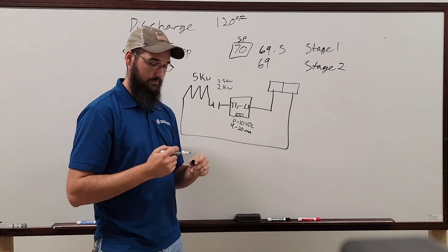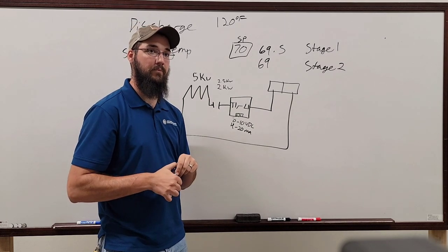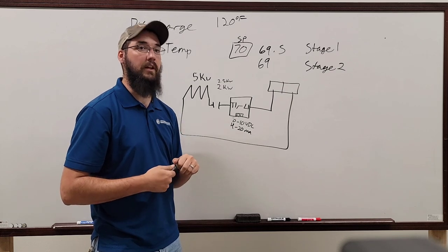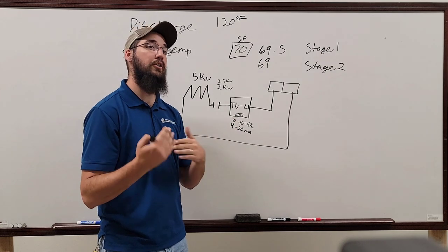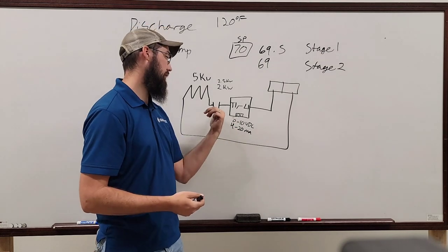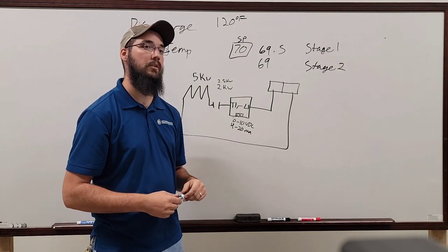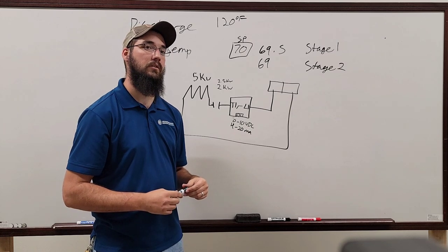So as soon as you get a call for heat, the contactor is going to slam, but your SCR is still going to regulate. Yes. And that's one way to know if you have a heat call: if all your heat safeties are closed, this contactor will close. If not, you have a control voltage issue.